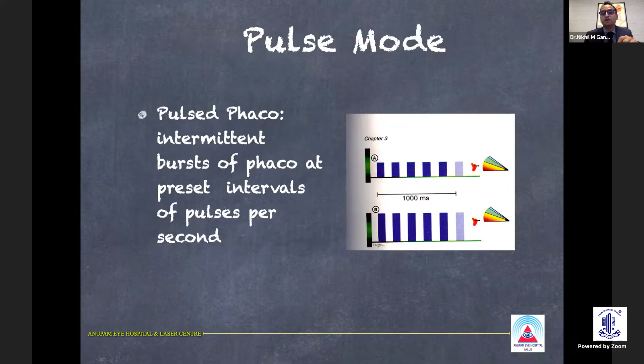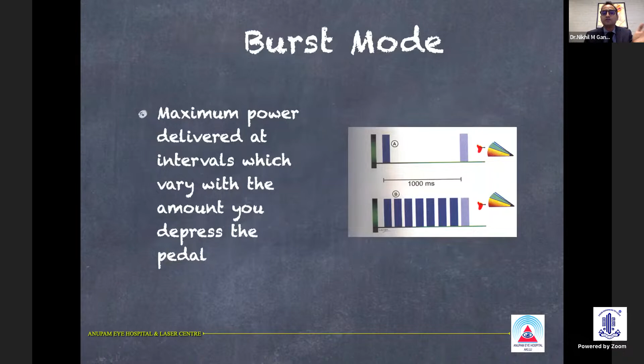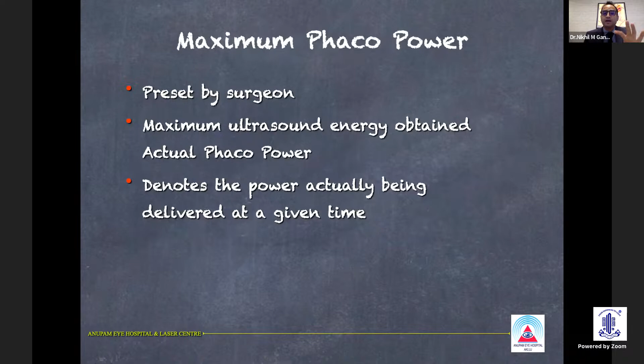So there is something called pulse mode, which gives intermittent bursts of Phaco at preset intervals of pulses per second. And in burst mode, maximum power is delivered at intervals which vary with the amount you depress the pedal. Maximum Phaco power, or you can say continuous mode, is preset by the surgeon, and maximum ultrasound energy is obtained by the actual Phaco power.